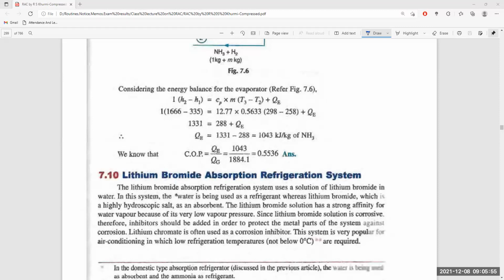Now, yesterday we started the lithium bromide absorption refrigeration system. This means we are using lithium bromide instead of ammonia. Lithium bromide absorption system means a solution of lithium bromide in water. So, refrigerant, a solution of lithium bromide in water.